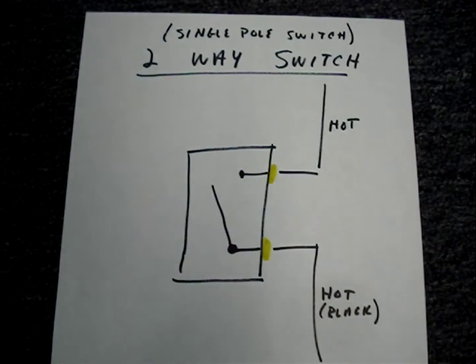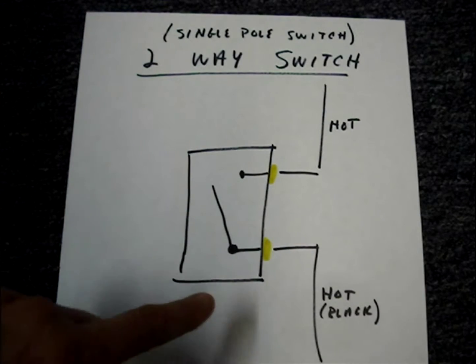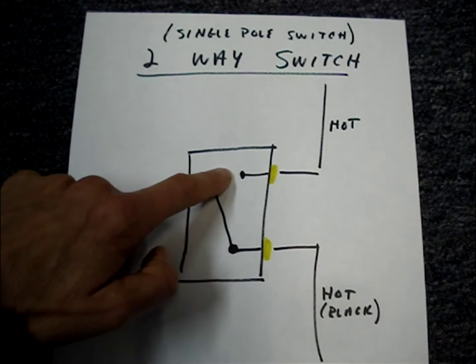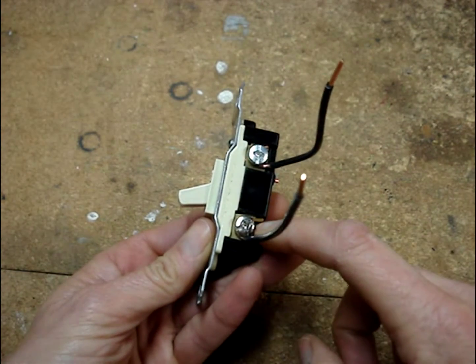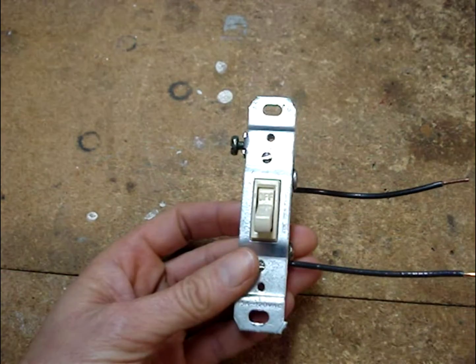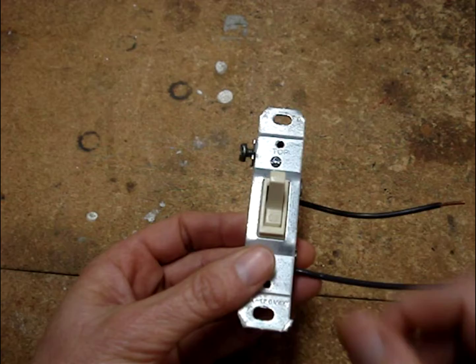A two-way switch, also called a single-pole switch, turns lights on or off from just one location. The switch simply opens and closes, switching the hot leg of power to the light. A two-way switch has two silver terminals and a ground terminal, and the toggle switch says off and on.